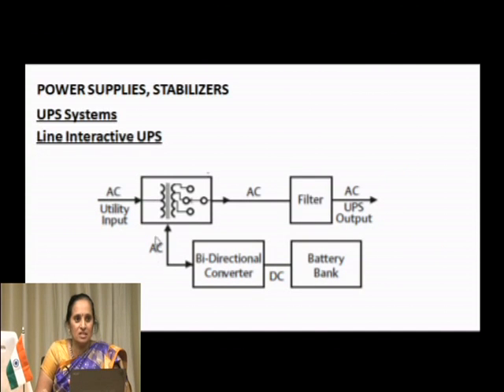This is one special device used in a line interactive UPS, as shown in the block diagram. It is not a normal transformer, it is a buck boost transformer with various tappings. You can increase or decrease the number of windings depending on the amount of voltage you require, tap it, filter it, and get the AC output. At the same time, there is a bidirectional converter here, AC to DC or DC to AC, which charges the battery bank. So when the main power goes off, this battery bank comes into existence and supplies the converted power.